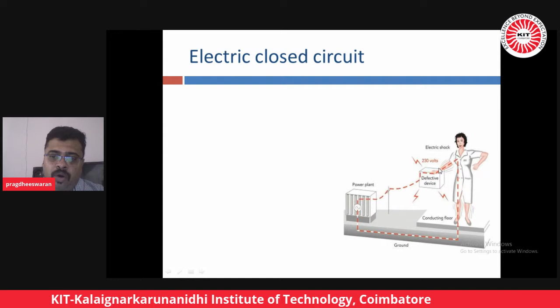We have to understand what leakage current is here. The leakage current is the jumping of excess electrons from the equipment's body. Every equipment is connected with multiple boards. Nobody can make a medical equipment or any equipment without a leakage current. Any equipment which gets connected to the AC mains power will have some kind of jumping of electrons. That jumping of electrons from all the boards, capacitors, insulation materials, power supplies and transformers, those cumulative currents will come out of the board, which requires to be eliminated out of the machine. Okay, there should be a proper way out for the leakage current.